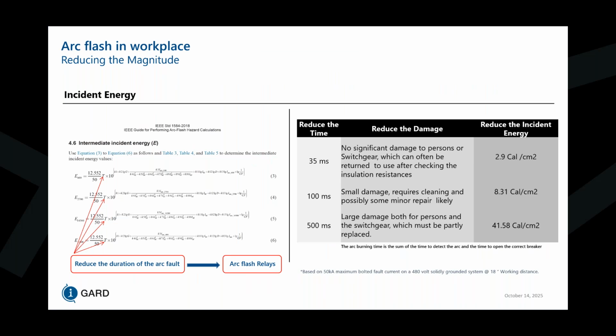So if we reduce the time to 35 milliseconds, for example, there's no significant damage to person or switchgear, which can often be returned to use after checking the insulation resistances via measuring. So we reduce the incident energy to 2.9 cals per centimeter squared. For 100 milliseconds, there's small damage, requires cleaning and possibly some minor repair, and we're reducing the incident energy by 8.31 cals per centimeter squared. And if we are reducing to 500 milliseconds, there's large damage both for person and the switchgear, which must be partly replaced, which is at 41.58 cal per centimeter squared.